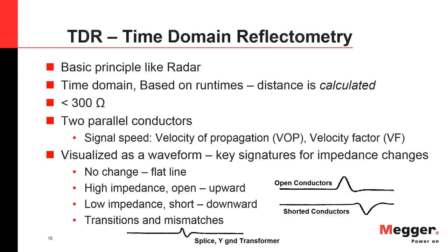And so if you have very low resistance faults, you can always hook up the radar and use the TDR and hope you will find a short or a low impedance situation without even turning on any high voltage. Also very effective with the TDR, which is a basic method I just want to repeat a little bit, is the phase comparison method. If you have three conductors or three phases, you can always take three measurements. Let's say if you have A, B, C, you can take a measurement A to B, B to C, C to A. And by comparison, you can also find which phase is faulted.